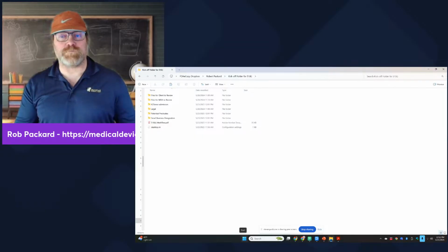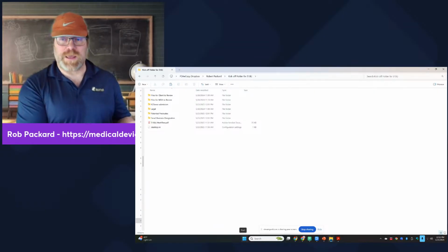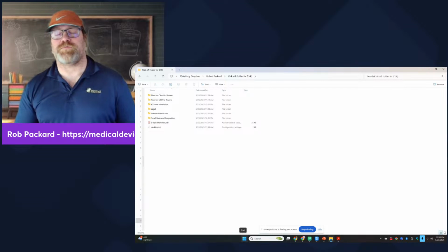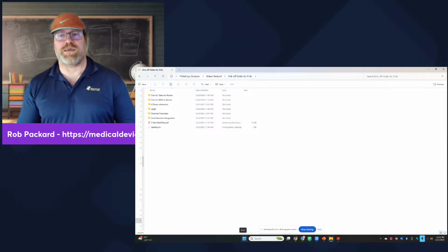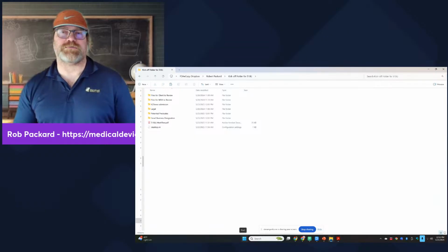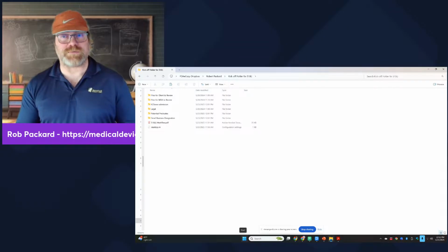They still use the same forms, but you have to attach the full tax return and the small business designation and upload it to the FDA if you're a U.S. company. And if you're a foreign company, you're just attaching the international version of it, which is 3602A. And on the back of it, it has you sign, date, and stamp from the National Tax Authority saying that the numbers are accurate for the taxes. And then you upload that to the FDA's CCP portal, and that begins the small business designation request process. And it's supposed to take 60 days.